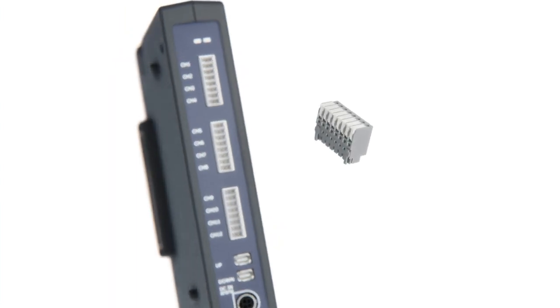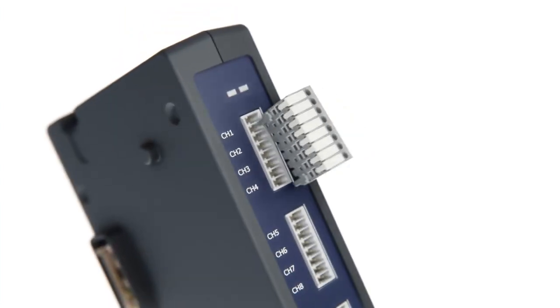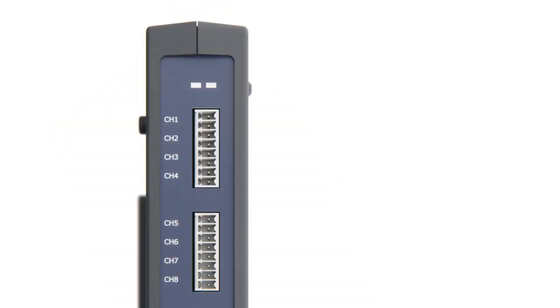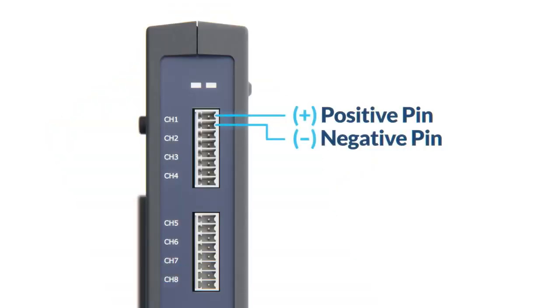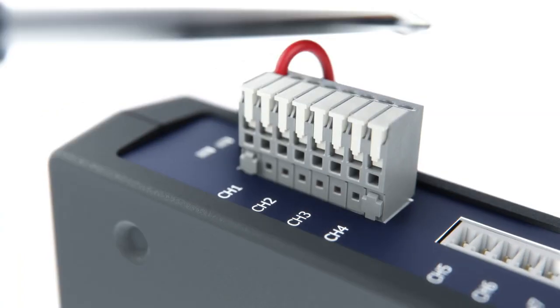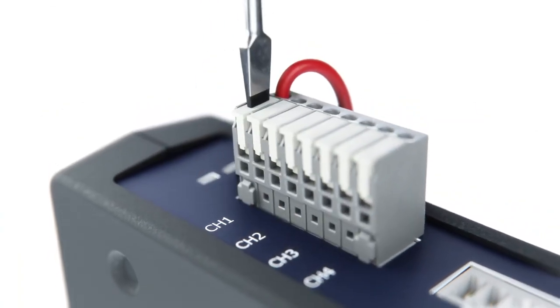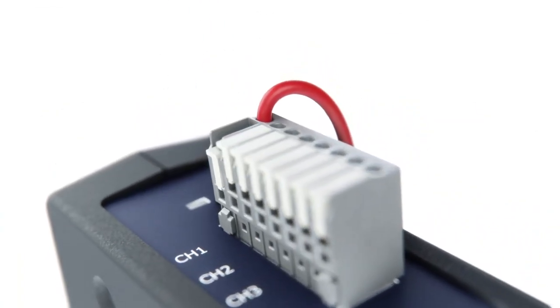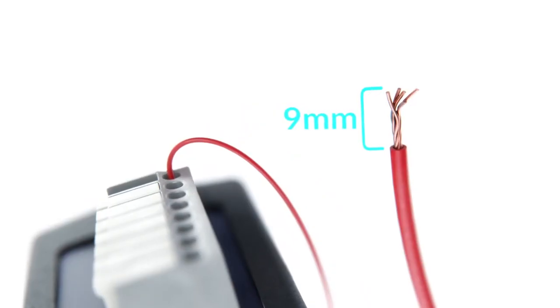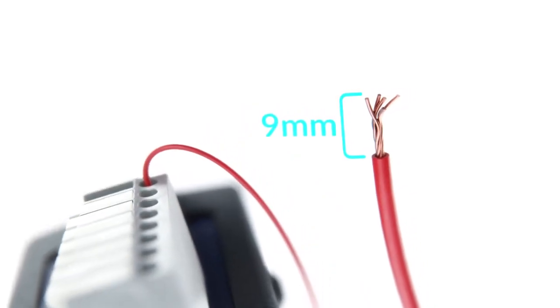When connecting the dividing terminal block, make sure the block is inserted as far in as it can go. The pin layout of each channel has one positive pin above a negative pin. To begin wiring, push the white bar using a driver or other tool to lock it in place. The dividing block's ports can receive American wire gauges of 16 to 26 and require a 9mm length of stripped wire for a proper connection.